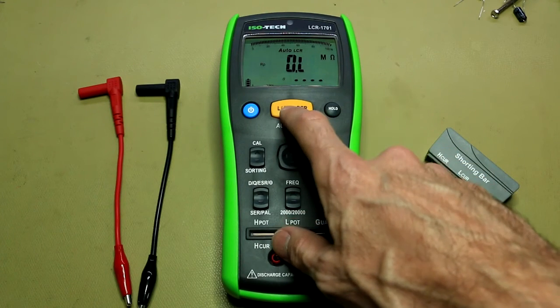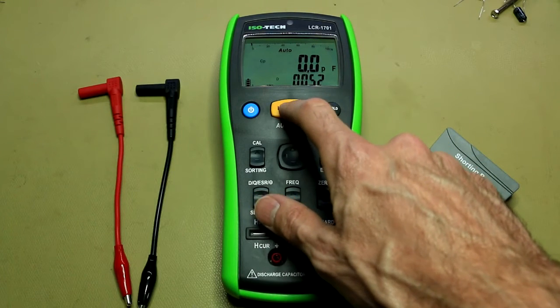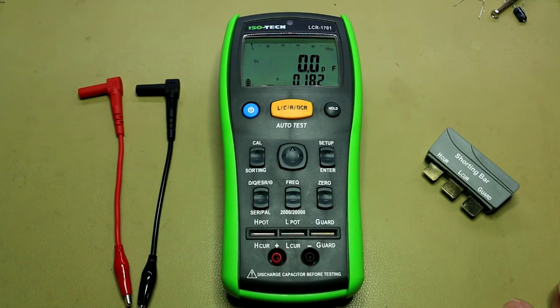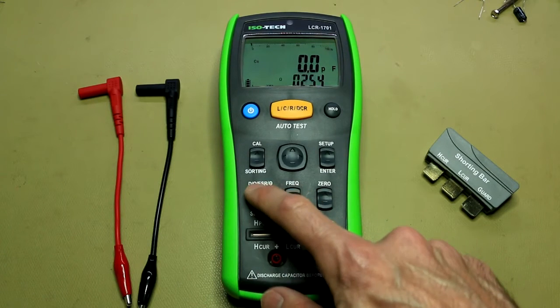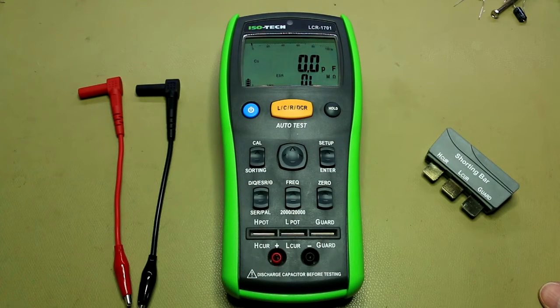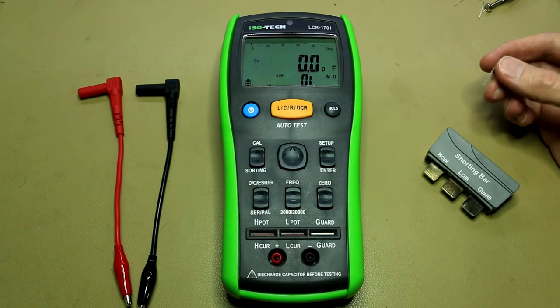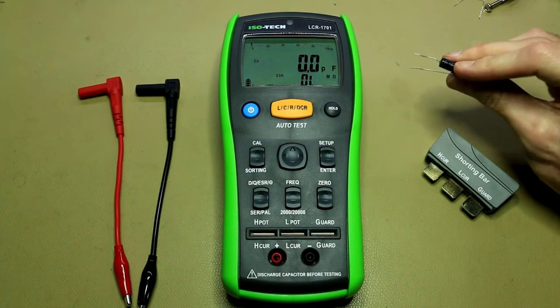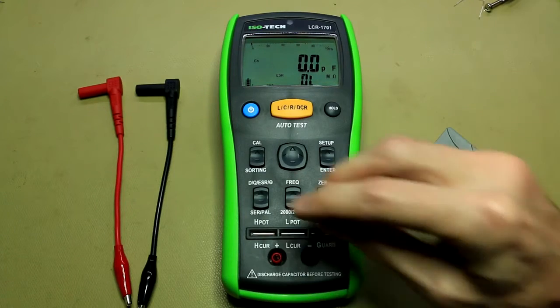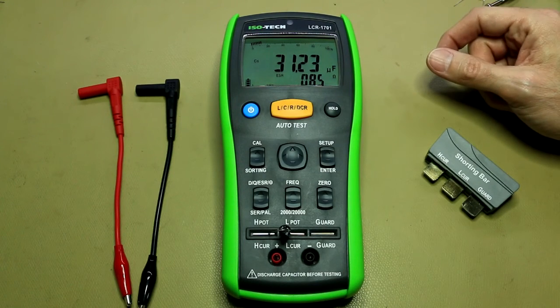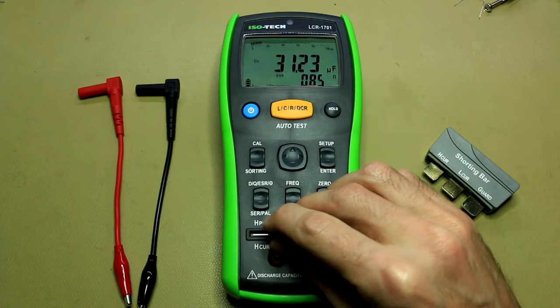You can actually now, say for instance, go to capacitive mode. There's the parallel mode. There's serial capacitance. And you can see it's sitting at 0 picofarad. It's measuring D value now. You can switch to ESR. It's not measuring any component at the moment. So let's plug something in and let it measure it. Okay, you can see that it's on the picofarad scale. So here I've got a 33 microfarad 16 volt capacitor. It's an electrolytic. Let's plug it in. And there we go, 31.23 microfarads. You can also see it's measuring the ESR at 0.85 ohms. So this capacitor looks to be good.